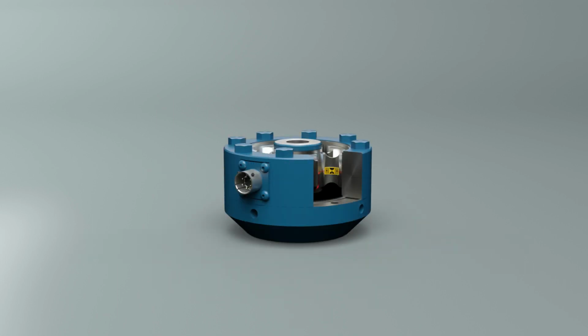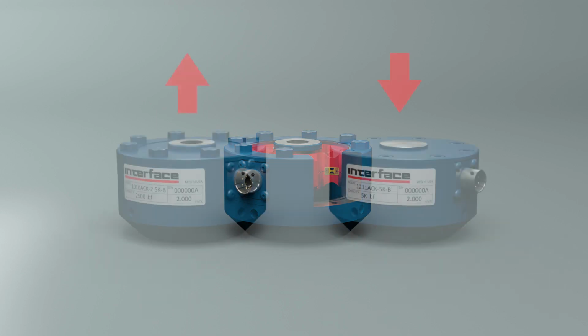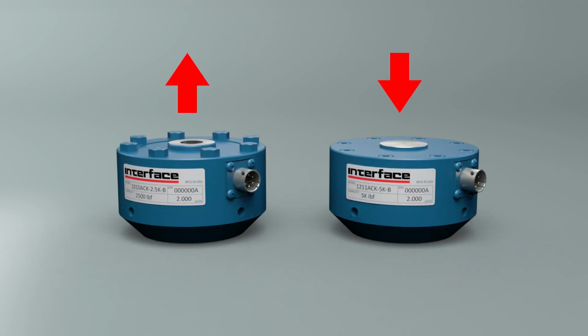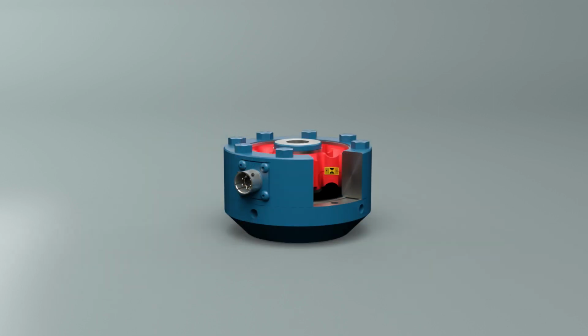Creep happens when a force is applied to a solid material within its elastic limit. The resulting deflection will increase very subtly with time if the force is held constantly. This is true whether the force is in tension or compression. This phenomenon is called creep, and by definition, is not permanent but is recoverable. The signal from a load cell exhibits this creep, and therefore it should be understood in all load cell applications.